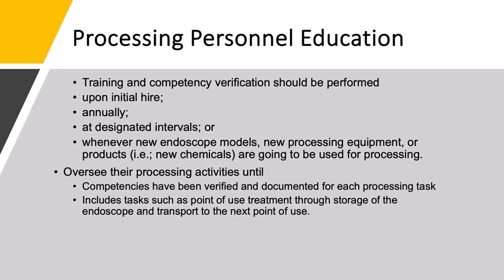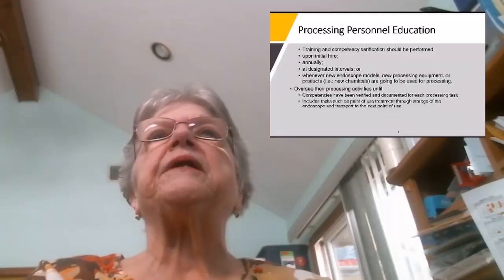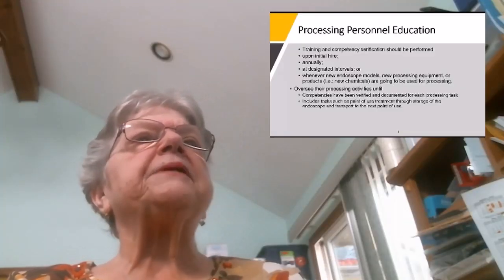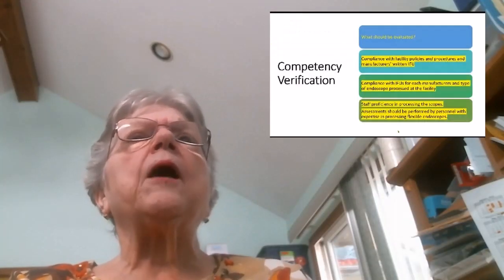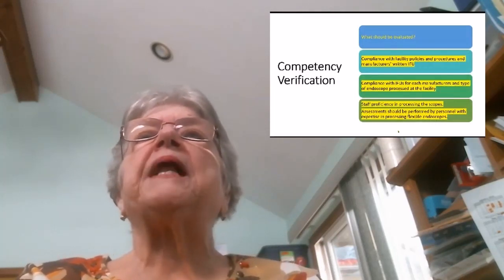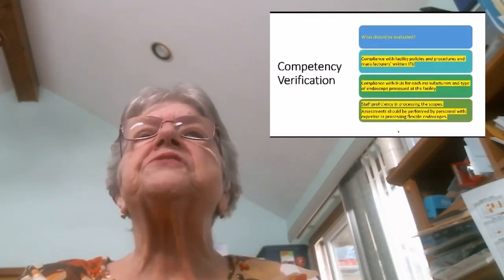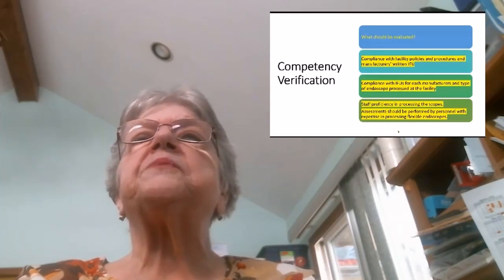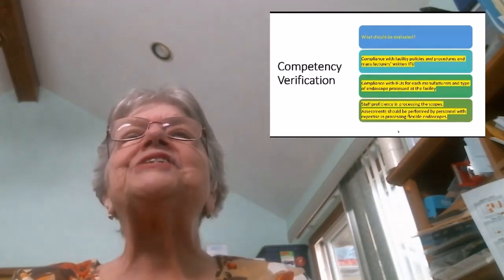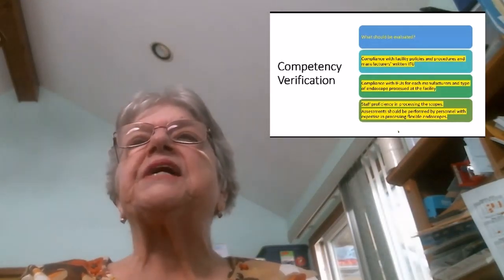Oversee their processing activities until competencies have been verified and documented for each task, and include tasks such as point of use treatment through storage of the endoscope and transport to the next point of use. For competency verification, what are we looking at? Well, is there compliance with your policies and procedures and manufacturer's instructions? Do you have compliance with instructions for each manufacturer and type of endoscope processed at the facility?